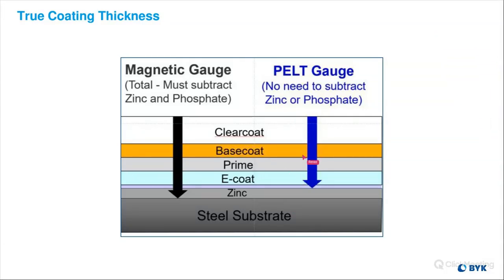If you were to compare PELT measurements to magnetic gauge measurements, you would see that the thickness of the E-coat would be higher on the magnetic induction side, because it would include that pre-treatment, the zinc and phosphate, whereas the PELT gauge gives true E-coat only.